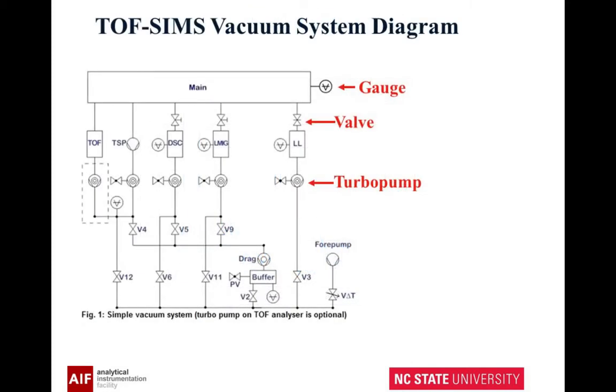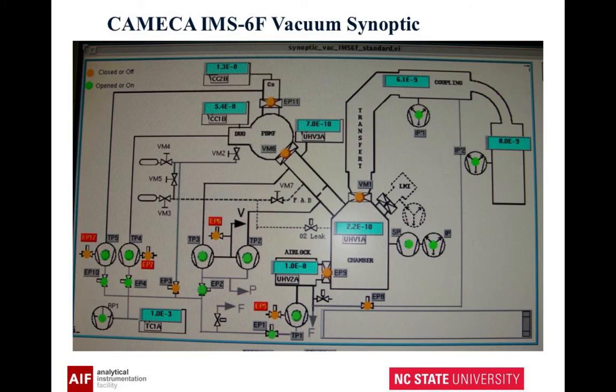You should also have a diagram of your system. These are called vacuum synoptics, and you can easily google simple examples. There's a symbol for a turbopump, a valve, and a gauge. By having it written down — especially if you're working in a group — you can make sure the information is passed along to the next person. Some of these vacuum synoptics are live, so if I click on this it opens that valve, or it will turn off that turbo pump. You have to be careful: if I click on the wrong one, I may vent the system.